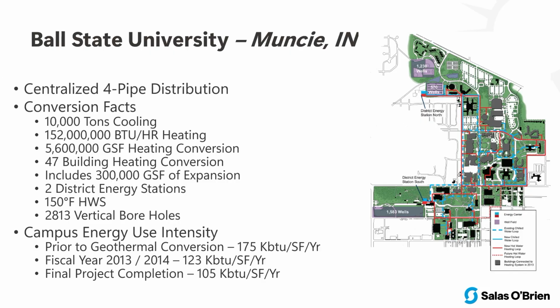This particular 4G system here does simultaneous heating and cooling, and that's where you gain the most efficiency in these types of systems. With 4G, the best efficiency gain is when you can take all that simultaneous load and do it with one lift, and your COPs are now 8 to 10, because you're doing 2 things with one lift. That's where that big efficiency gain comes in. And as Mike mentioned, getting to the lower temperatures is huge, because now we can use heat pumps.